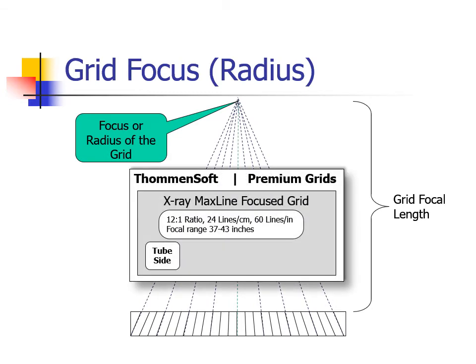Along with the center of the grid, most grids have a label designating the important characteristics of a grid. Here is a fictional company's information label. This is a 12 to 1, 60 line grid and can be used within a range of 37 to 43 inches to prevent cutoff artifacts. This grid would probably be used in a table bucky that includes a reciprocating mechanism due to its low frequency.